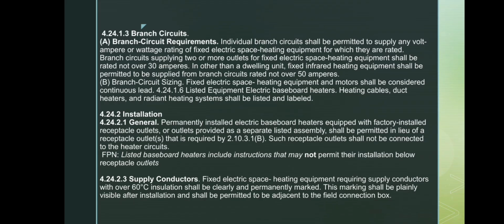General. Permanently installed electric baseboard heaters that have factory-installed receptacles may be used instead of the required wall receptacle, but these receptacles cannot be connected to the heater's circuit. Note, some heaters include instructions that do not allow installation below wall receptacles. Supply conductors: if the heater requires supply conductors rated above 60 degrees Celsius, the equipment must be clearly and permanently marked, and the marking must remain visible after installation.